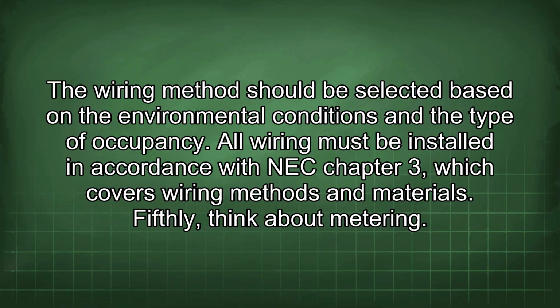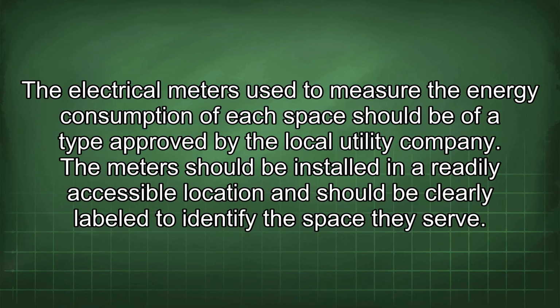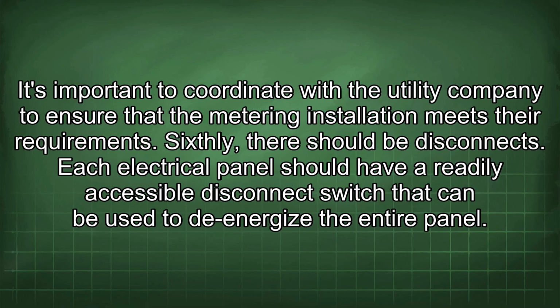Fifthly, think about metering. The electrical meters used to measure the energy consumption of each space should be of a type approved by the local utility company. The meters should be installed in a readily accessible location and should be clearly labeled to identify the space they serve. It's important to coordinate with the utility company to ensure that the metering installation meets their requirements.